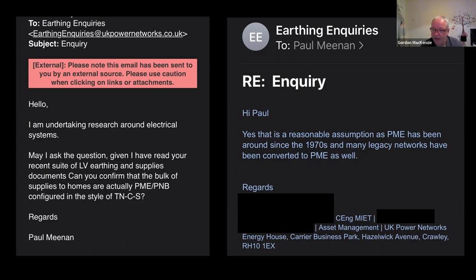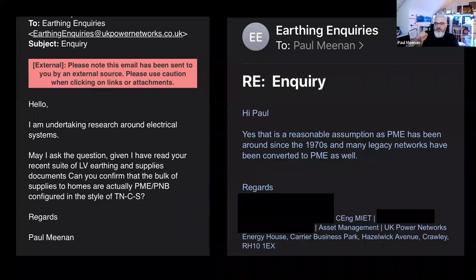So I'm going to be controversial here because I can see Paul's face. Is it fair to electricians to have to know what's going on in the network? But then again, is it fair for electricians not to know that if they're in a TNS looking installation, a 6mm bond isn't sufficient and it should be 10mm? Or should electricians be given guidance to make an inquiry at each installation to check with the DNO and have them verify it? Because I've just done that by email with UK Power Networks, covering the southeast of England, and one of their very senior asset management people confirmed it's been converted. So if I now have that knowledge, why am I putting TNS on a sheet if it just looks like TNS?